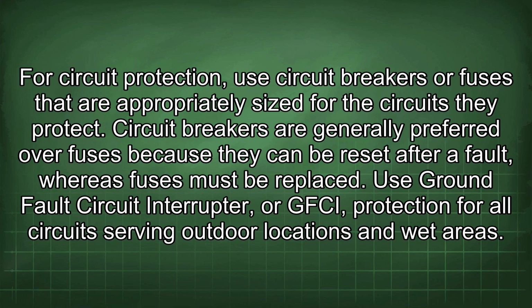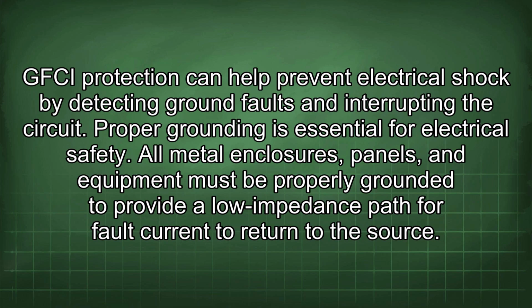Use ground fault circuit interrupter, or GFCI, protection for all circuits serving outdoor locations and wet areas. GFCI protection can help prevent electrical shock by detecting ground faults and interrupting the circuit. Proper grounding is essential for electrical safety.